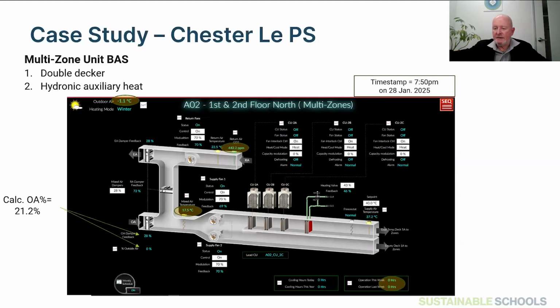Right. And this was about 7 o'clock yesterday evening, and you can see here, if Carolyn could move the cursor to it, the units were running. They've got variable frequency drives on the fans, which is great. In the evening, you had 442 parts per million. So that's a fairly low concentration, but everybody's gone home by then.